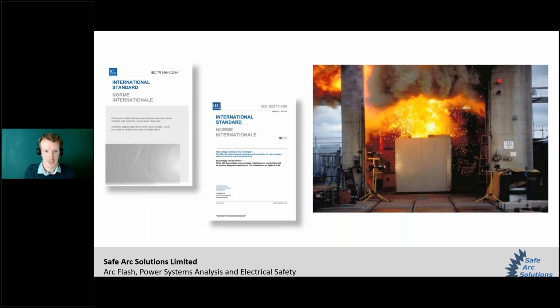There are solutions on the market which do reduce the arc flash likelihood or severity in equipment. This is referred to as arc resistant switchgear, and there's a couple of international standards which are shown on the screen here. One is for low voltage equipment and one is for medium voltage equipment. And this is really bringing in inherently safe design and trying to design out some of the risks of arc flash. It might be about better insulation around conductors. It might be around channeling the arc flash energy away from the operator. It might be segregating the compartments better so that you have less of a buildup of energy. But of course, these kinds of solutions really only apply to new equipment that you're going out and specifying today.